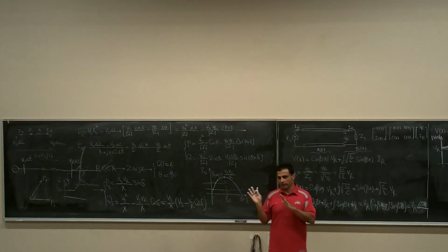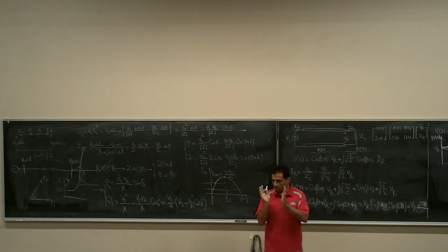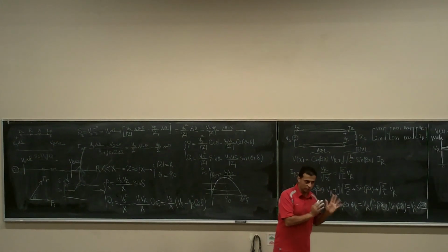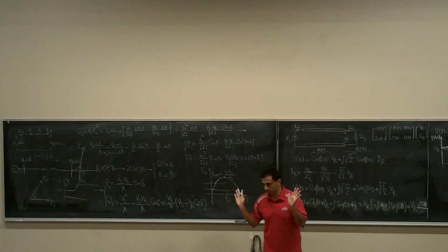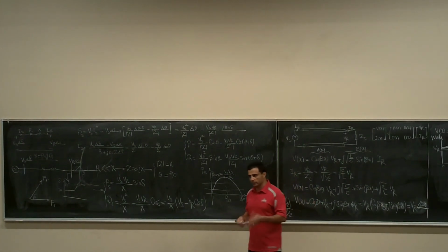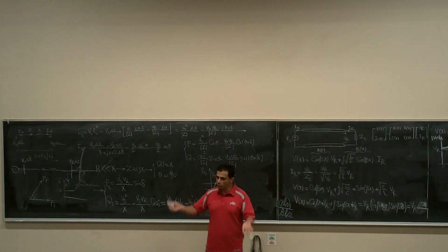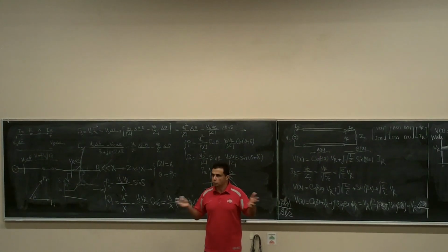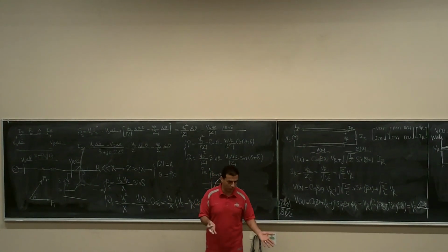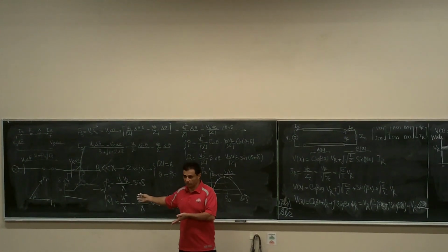If you are in islanding mode, as they call it, you should make sure that within a very short time, if you are going to stay hot and continue to generate power, you should disconnect. These are very advanced topics in the IEEE communities. They are talking about this because there are lots of stability issues to consider in coming up with the new rules. How should we write the rules so everybody follows them and does not cause problems? First of all, they can operate and will not cause problems for the rest of the system.